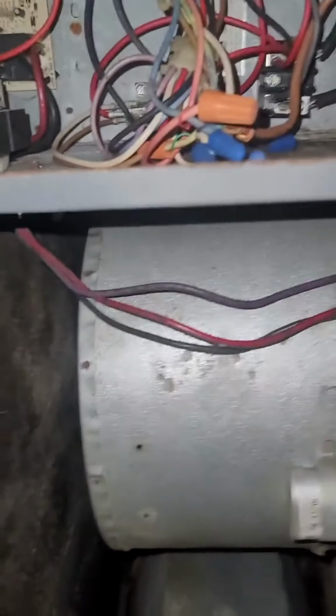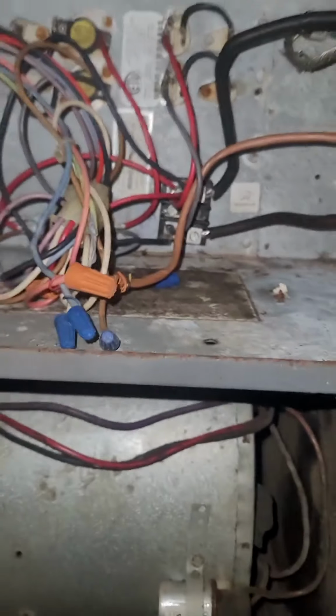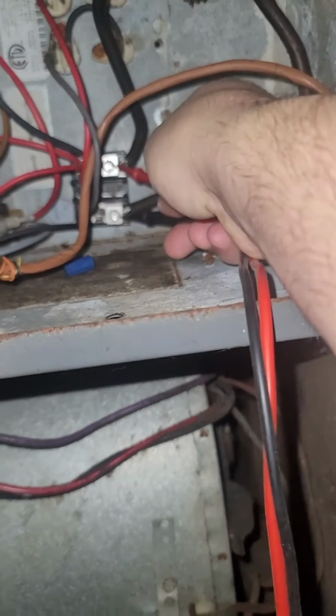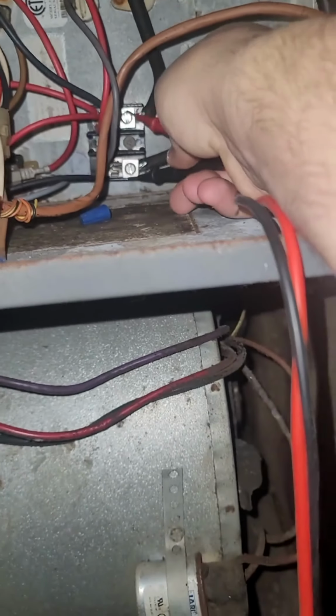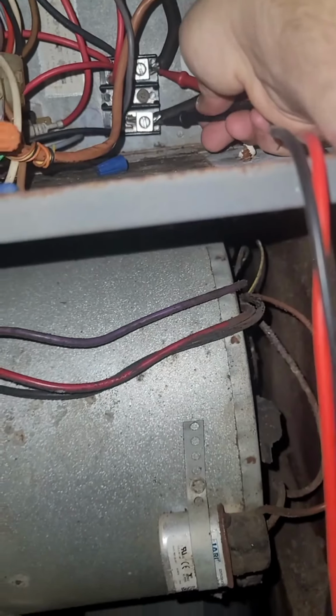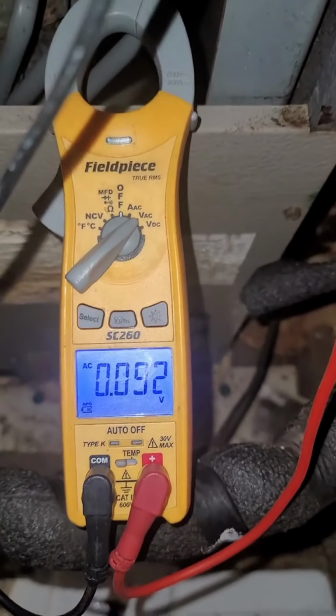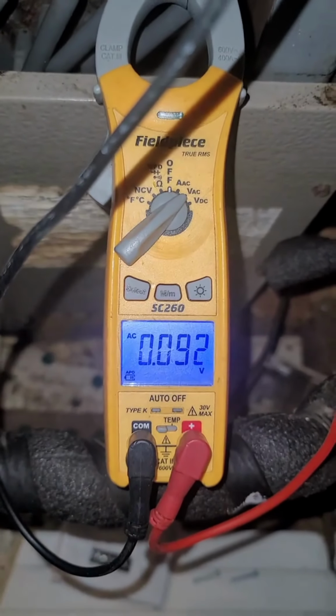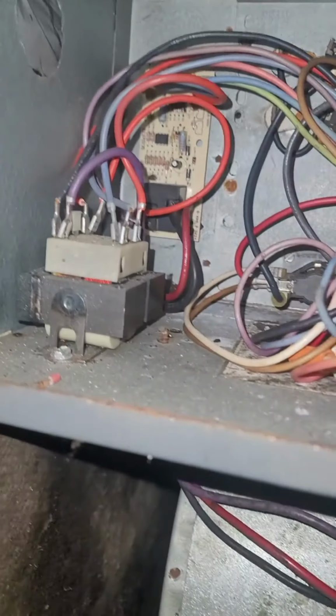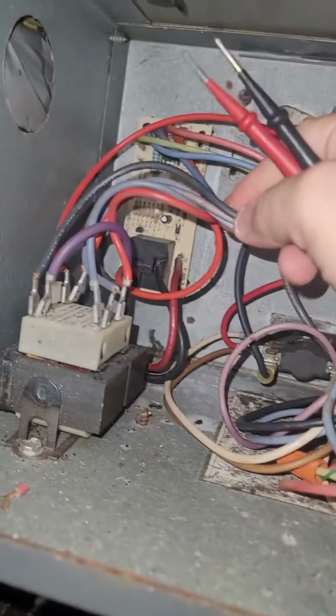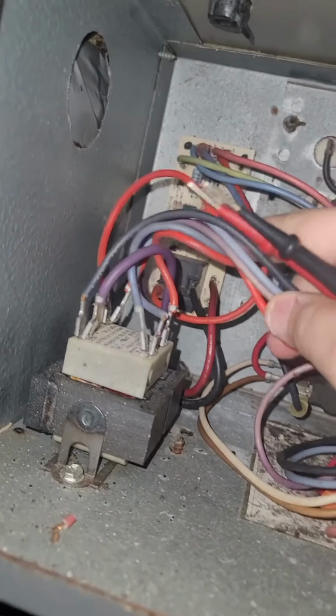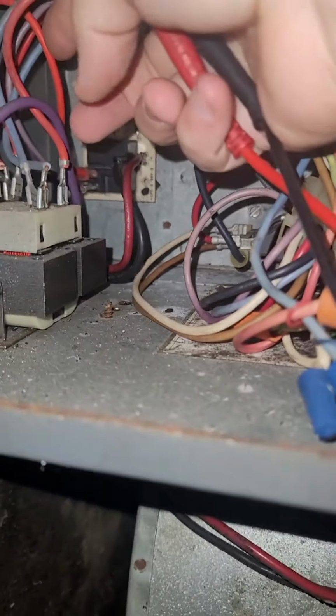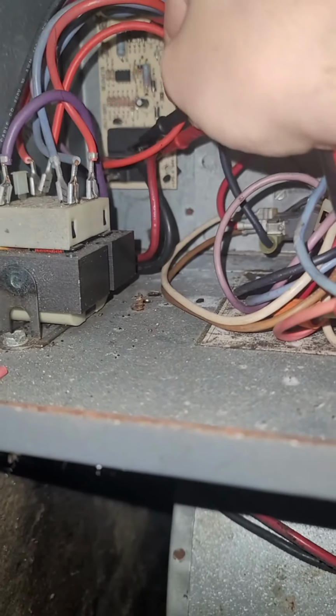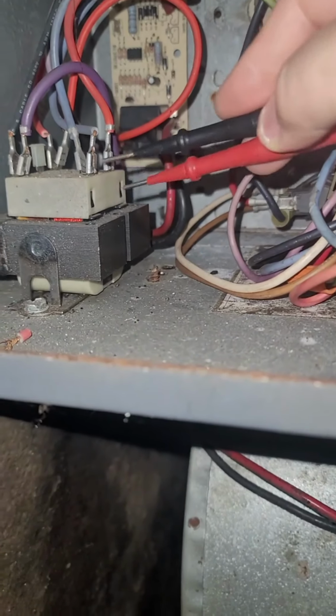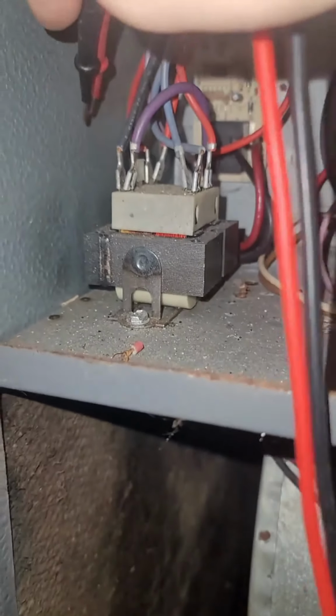Don't get overwhelmed about all the wires. It's really simple. I'm going to walk you through it one wire at a time. Those two big black wires in the back are high voltage wires. You're going to check power to those. We know that power's off outside, maybe a disconnect or a breaker's turned off. I'm looking at the circuit board to see if there's any small fuses on it. Sometimes on different circuit boards there's little bitty small fuses. You'll want to check those.